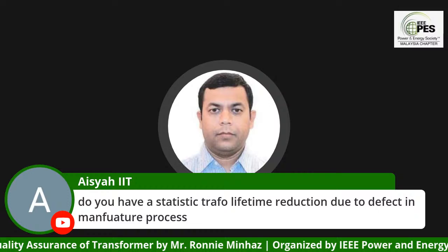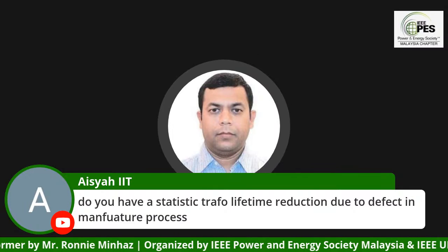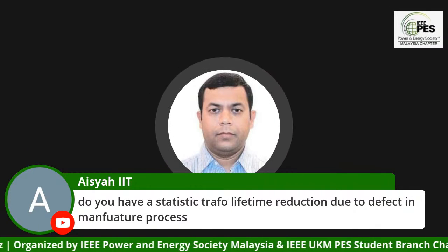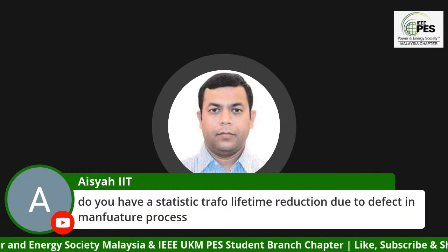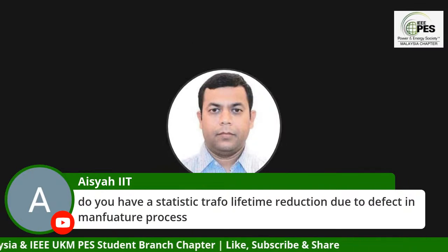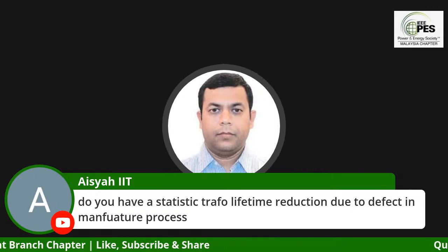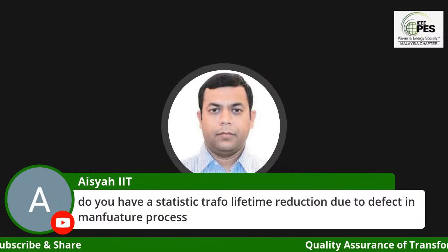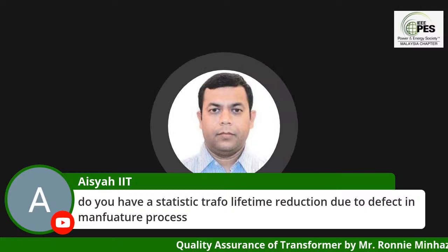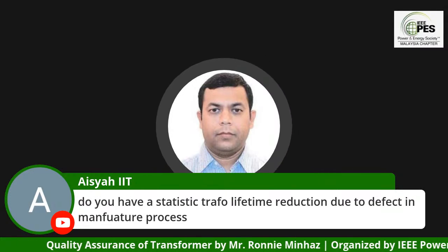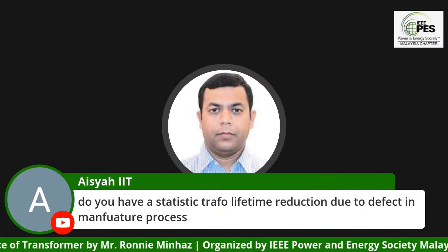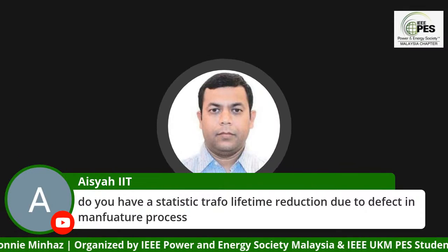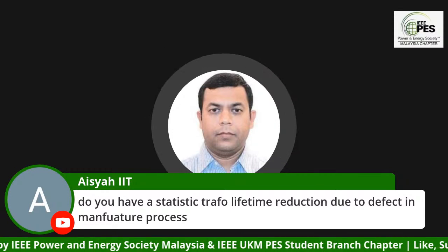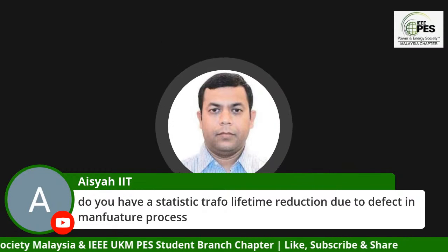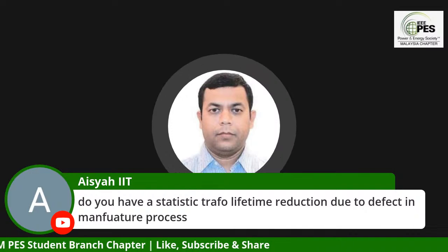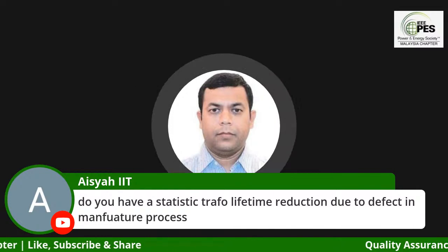So what I have noticed in the electric utility when I was working as an equipment engineer, in our fleet we had 40 substations, and we have transformers, from 80 years old transformers all the way to 2 years old transformers. Over the period, the question comes why the transformers that we had lasted 80 years, and at the same time we had issues of tank leaking. Some newer transformers failed due to short circuit, right?